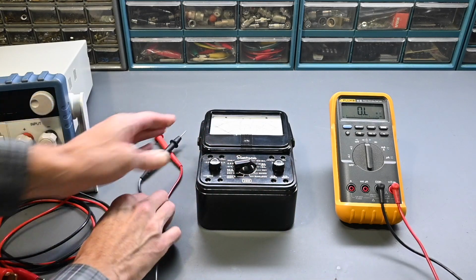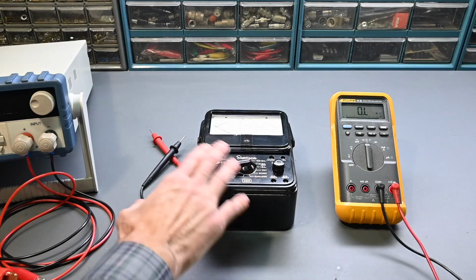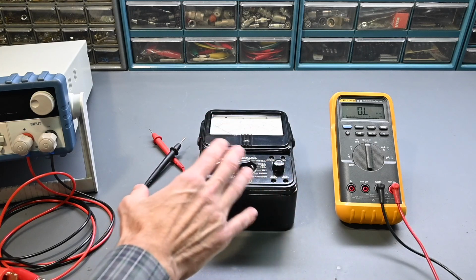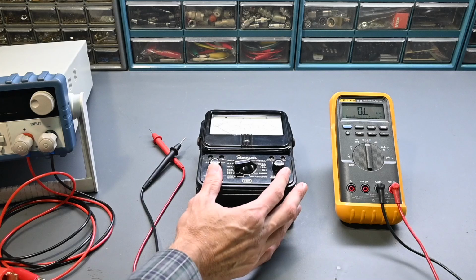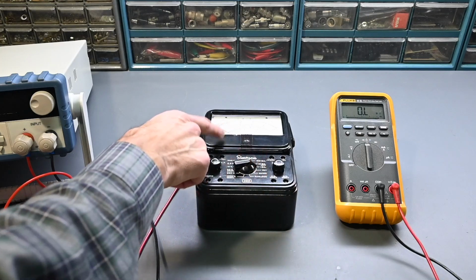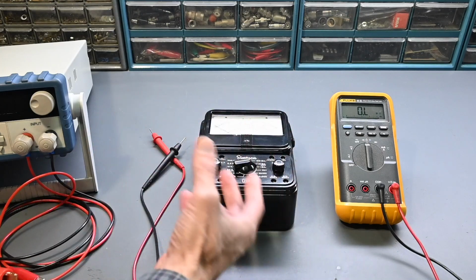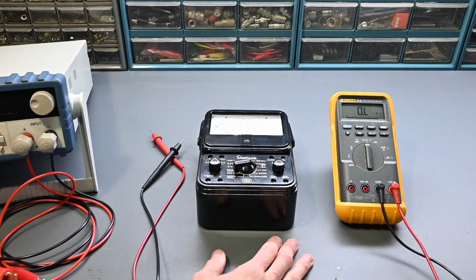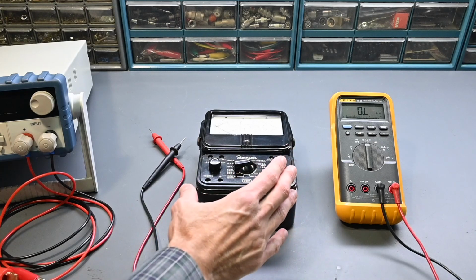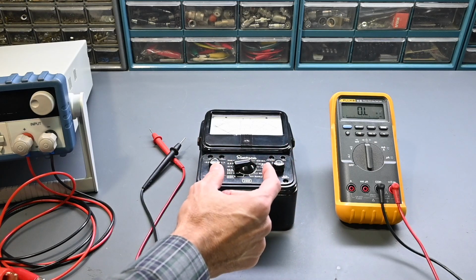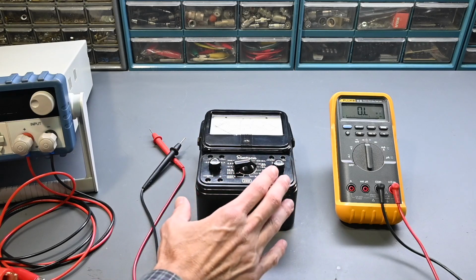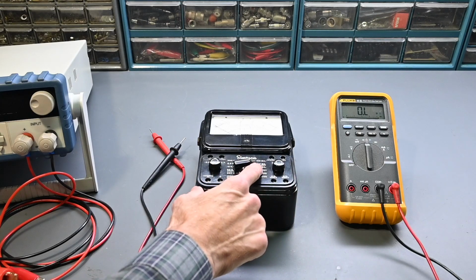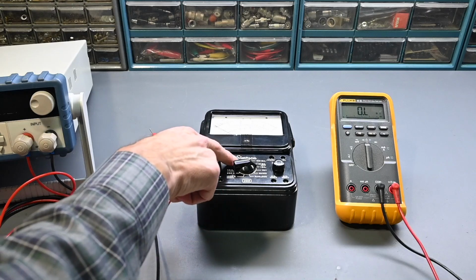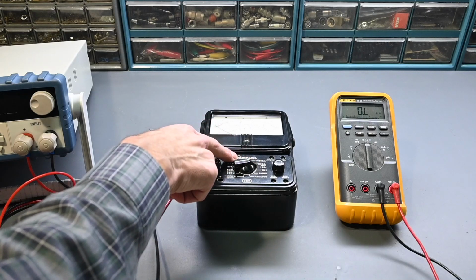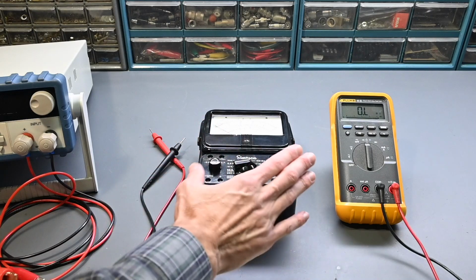And the reason is because in this meter, it's a passive design, and it needs to have voltage drop across the shunt to have enough voltage to drive the meter. There's no amplification, no active circuitry in a meter like this. So to get enough voltage drop, you have to have a large enough resistance because 1 milliamp is a very, very low current. So if you only had 1 milliamp flowing through the low resistances that we saw in these other ranges, you wouldn't develop enough voltage drop on those shunts to have any meaningful reading.